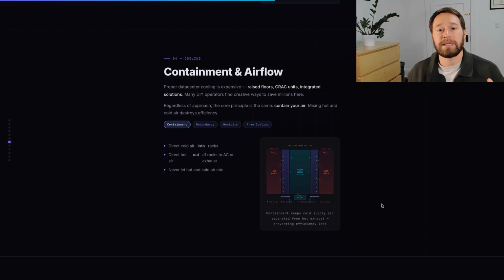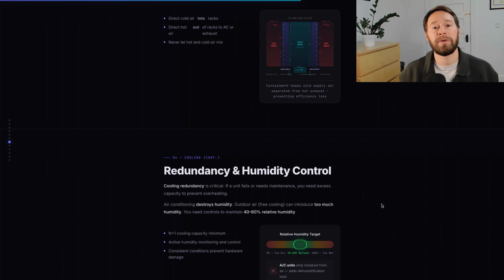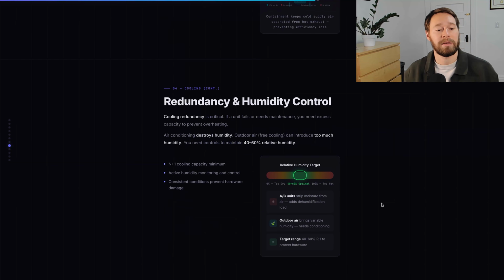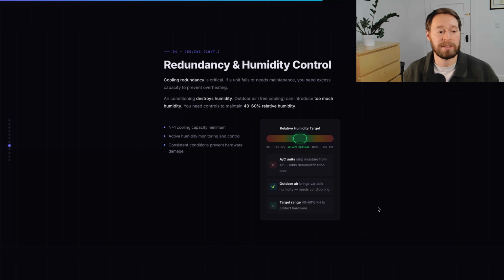To achieve redundancy in these systems, you use more units than you actually need. You'll see this notated as N+1 or N+2, referring to how many extra redundancy components you're adding in case you need to do maintenance on one or something fails. That notation comes from the storage world, where you talk about how many disks you can lose before losing data, and it's also true in the air conditioning world.